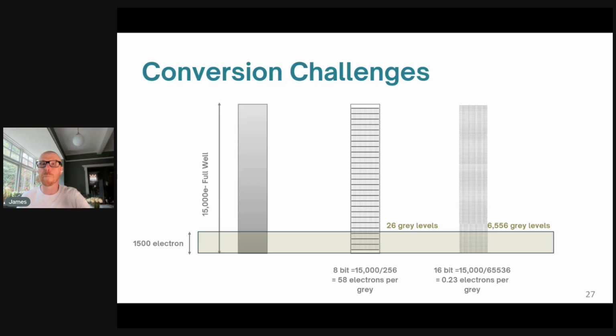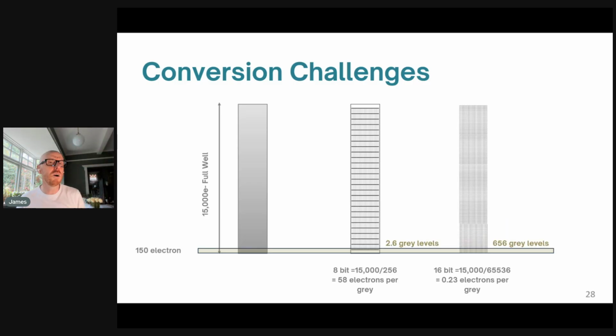My 65,000 levels are going to spread out nicely across the 256, so I'm going to look like I have no big steps. And again, if I took it down to 150 electrons, well, my 8-bit camera with my 15,000 electron full well has 2.6. I got 3 gray levels. Now, of course, there's gain. Of course, there's ways of handling this. But this is a fundamental issue in some of the ways that we operate. When we turn on the camera, we don't have the scales. We don't have the nice images. Why? Because we're living at the bottom.